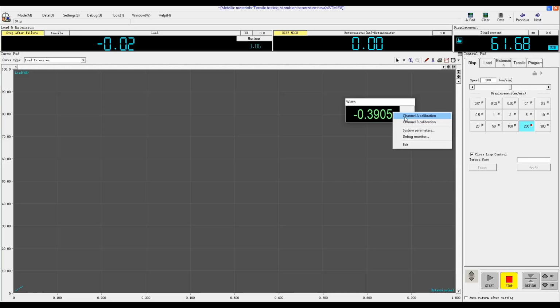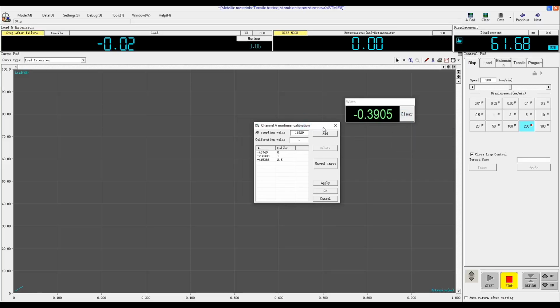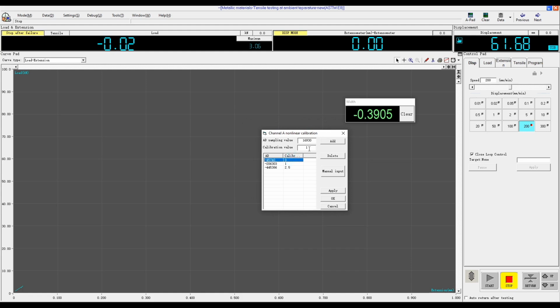Calibrate to 0.5 millimeters and click Add in the software. 1 millimeter, 1.5 millimeters, 2 millimeters, 2.5 millimeters. After adding all of the points, click Apply and click OK. In the software, you will see a window for the transverse extensometer. Right-click the window and select Channel A Calibration. Here you will see that calibrations have been conducted for 0 millimeters, 1 millimeter, and 2.5 millimeters, each with its corresponding sampling value. When calibrating for the first time, you may delete all existing values, input 0 in the calibration value field, and click Add.